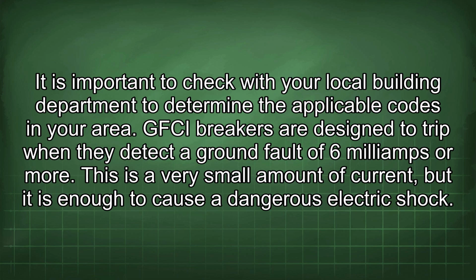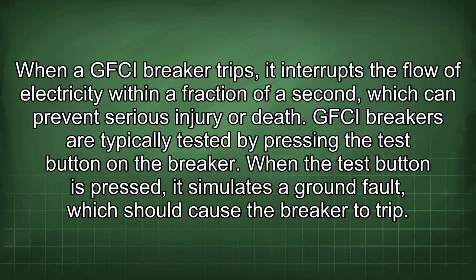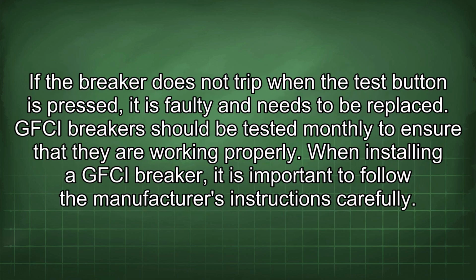GFCI breakers are designed to trip when they detect a ground fault of 6 mA or more. This is a very small amount of current, but it is enough to cause a dangerous electric shock. When a GFCI breaker trips, it interrupts the flow of electricity within a fraction of a second, which can prevent serious injury or death. GFCI breakers are typically tested by pressing the test button on the breaker. When the test button is pressed, it simulates a ground fault, which should cause the breaker to trip. If the breaker does not trip when the test button is pressed, it is faulty and needs to be replaced.